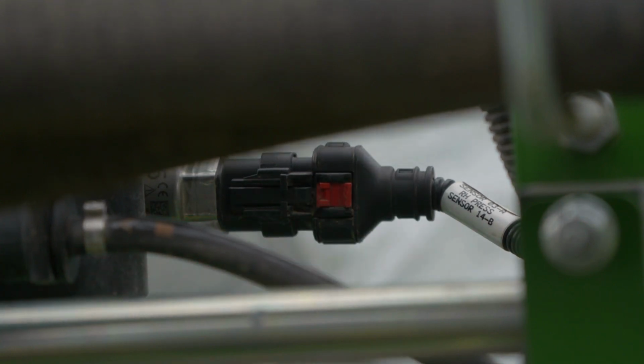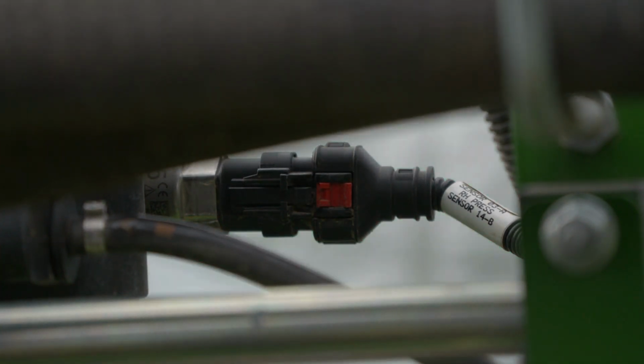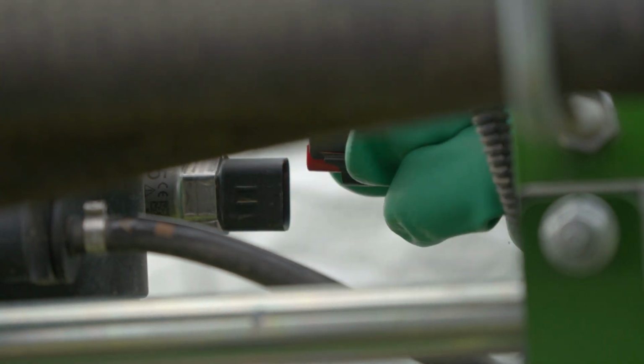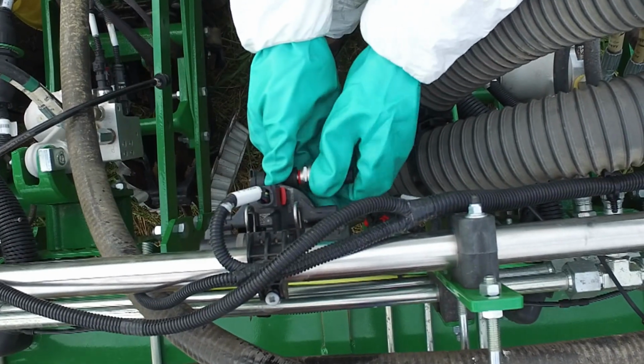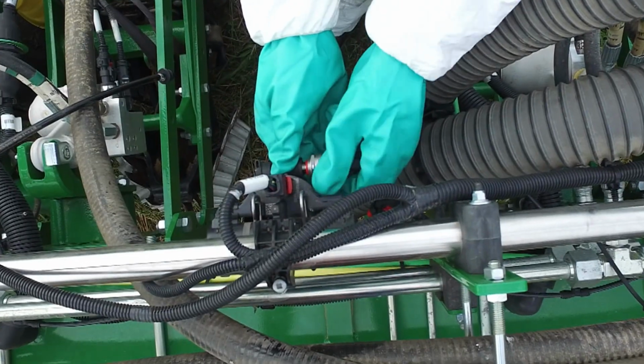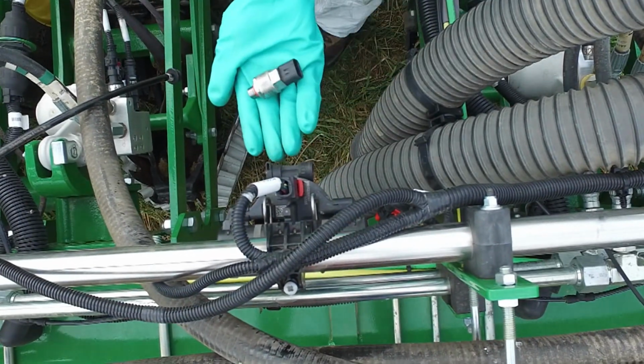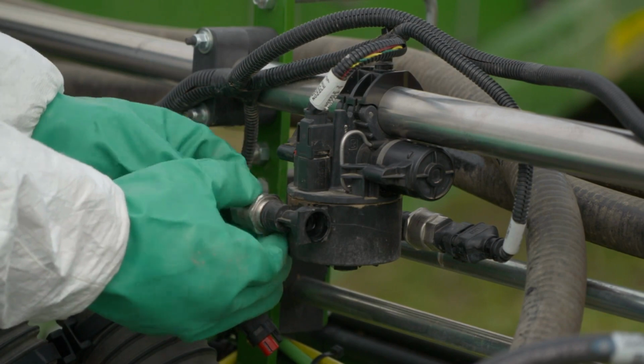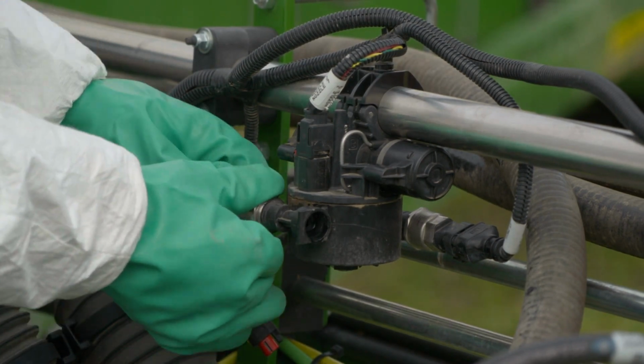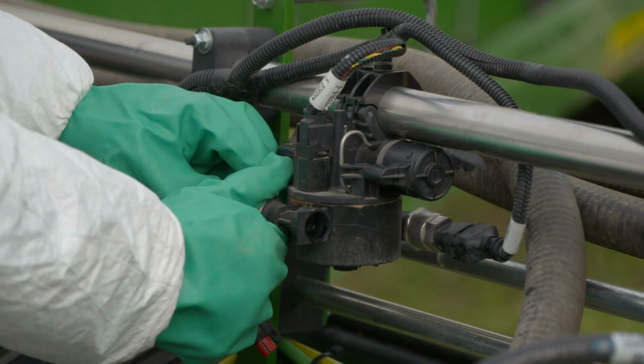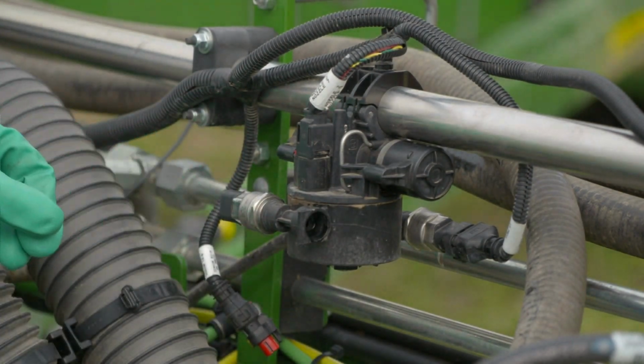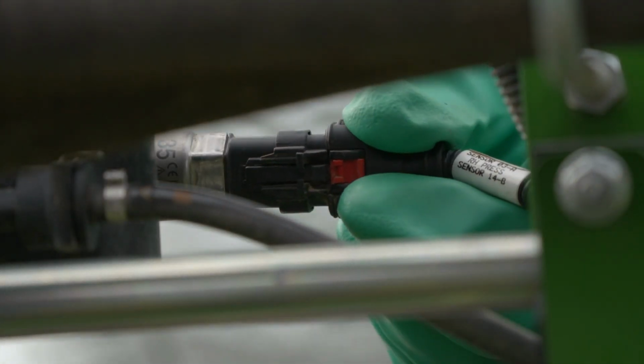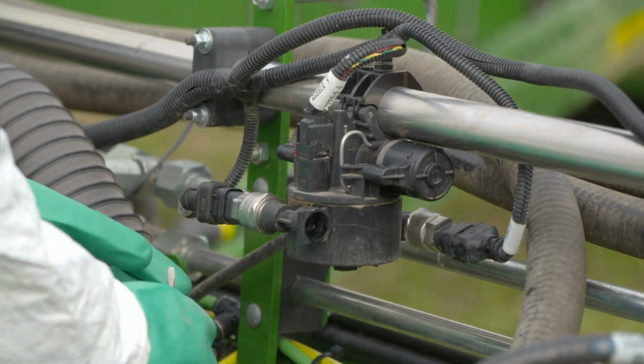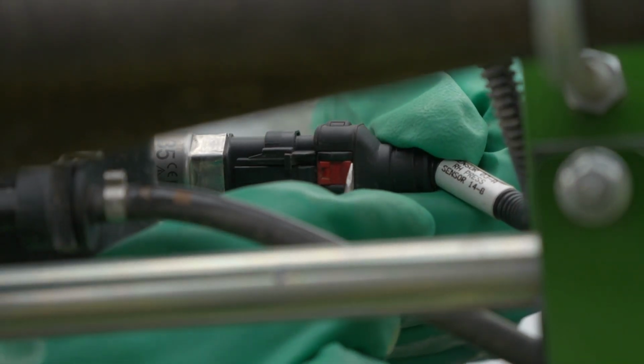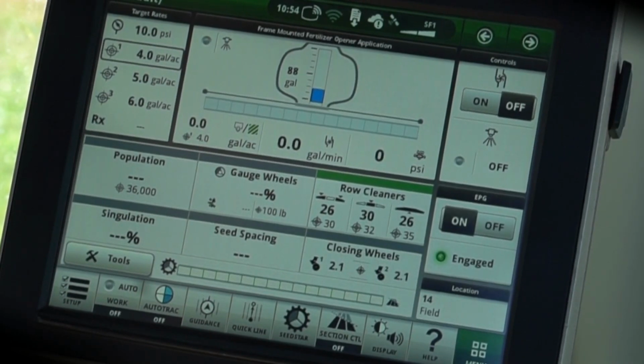First, disconnect the electrical harness by sliding back on the red lock and pushing in on the black retainer. Then, unscrew the sensor from the valve body. Clean the sensor as needed. Install the clean sensor. Attach the electrical harness. Make sure to seat the red lock. If cleaning the pressure sensor does not solve the problem, then the sensor should be zeroed.